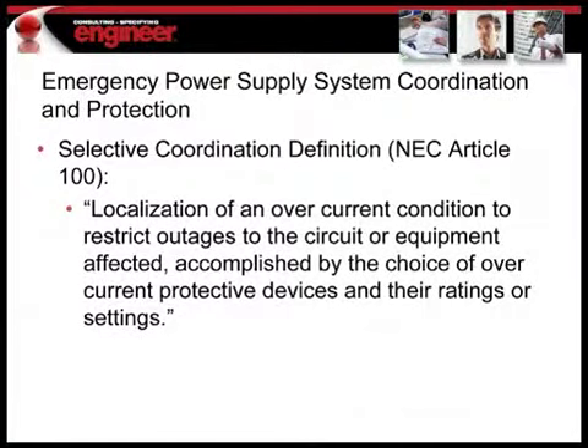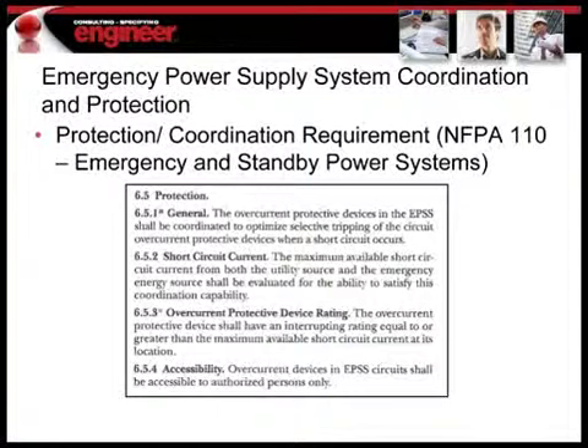Now, there are several codes out there that do require selective coordination, especially on the emergency side. NEC is one of those, and what it talks about is you want to localize an outage to the appropriate breaker, and this is taken from the NEC exactly, so you could take a look at that. I'll go into an example in a little bit. Also, one thing to keep in mind from a generator standpoint is that NFPA 110, which is the standard for emergency and standby power systems, includes a requirement that the EPSS must be selectively coordinated as well.